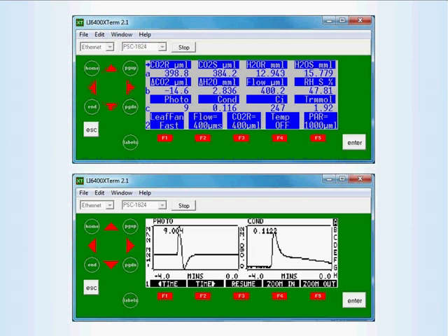Although in this example we have used the desiccant control knob setting to modify sample chamber humidity, in general changing the airflow rate has a bigger effect on sample chamber humidity. Elizabeth will explain this in more detail later in the presentation.